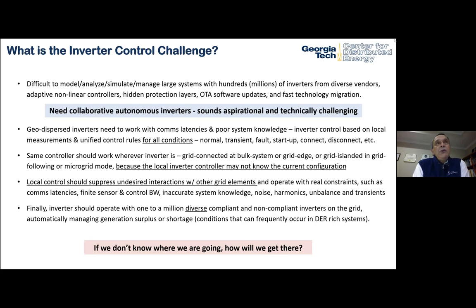So what does local control do? The lowest-level control really should suppress undesired interaction with other grid elements, whether it's other inverters, transformers, or capacitors, and make sure those things aren't a problem. In a real environment you have latencies, sensor and control bandwidth, noise, inaccurate knowledge - all of these are real things, and you need to be able to operate with all of that.